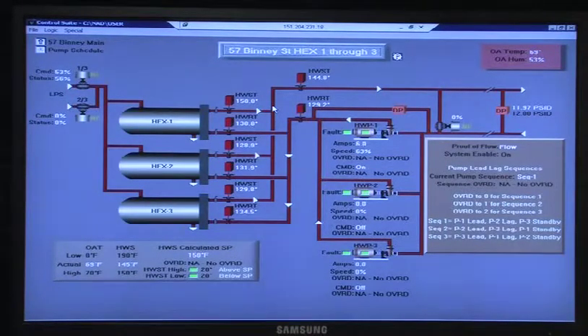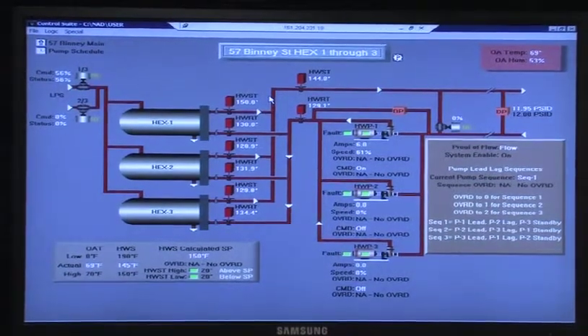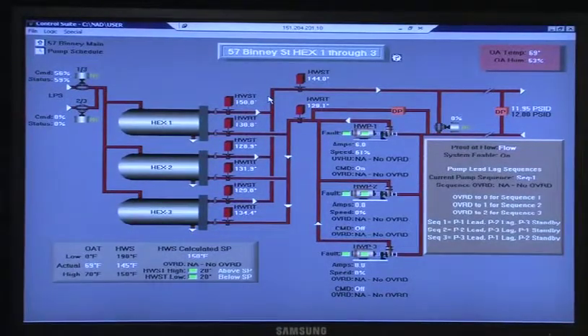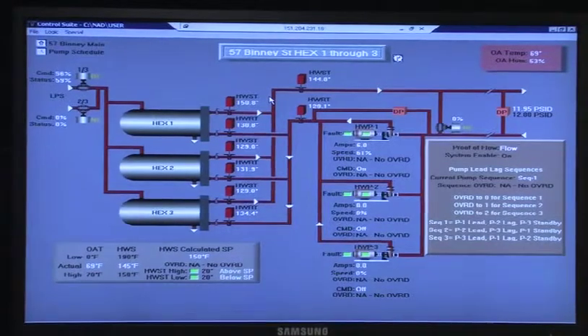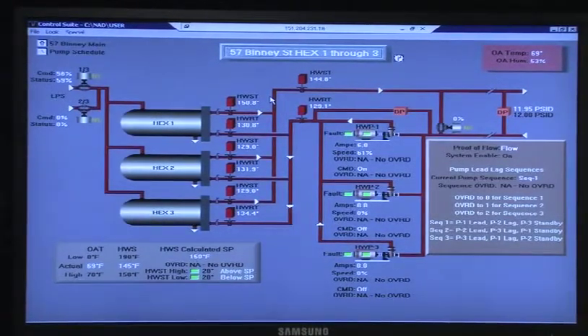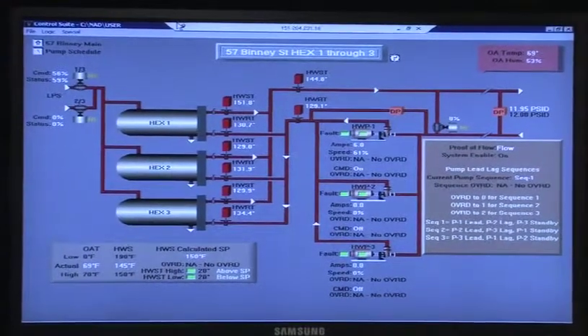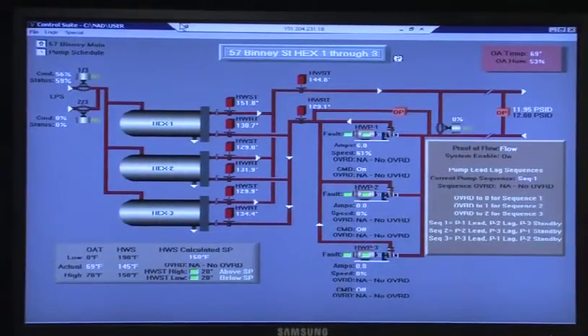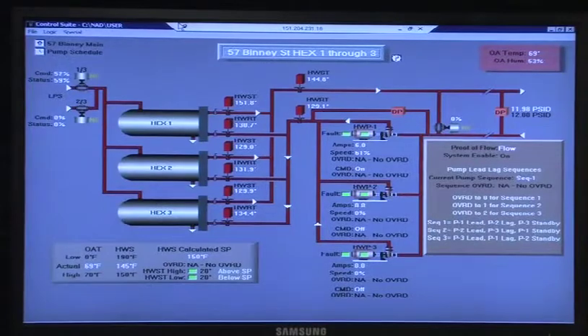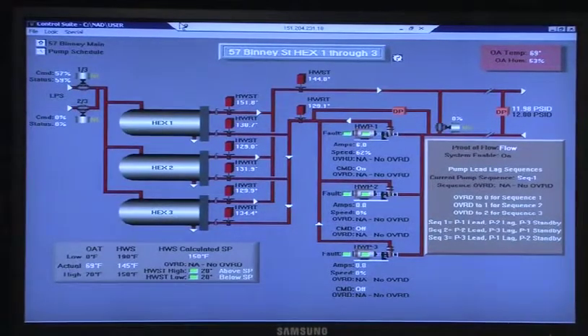I don't know whether or not that's the way you want to operate it. No, that's not the way. It's just going to circulate through. You're just wasting pumping. Well, it's not only that, you're mixing your discharge. You're just pushing the hot water through. Some of them might get heat losses, but then you're pumping water through something you don't need to pump it through, so you're just wasting pump power.